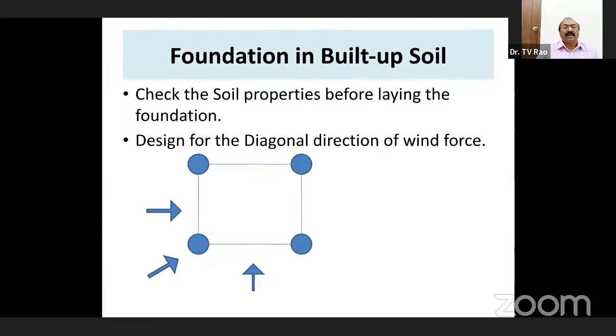There are other failures also. While considering the wind force, we have to consider the direction in 3 ways: parallel to the conductors, perpendicular to the conductors, and diagonal to the tower. If we consider the diagonal direction of wind force, one leg will be in uplift (tension), another leg will be under compression, and the diagonally opposite legs will be in neutral condition.